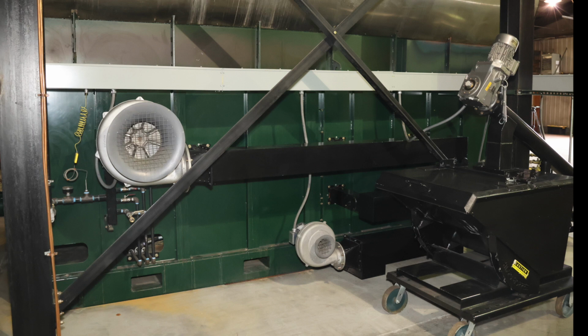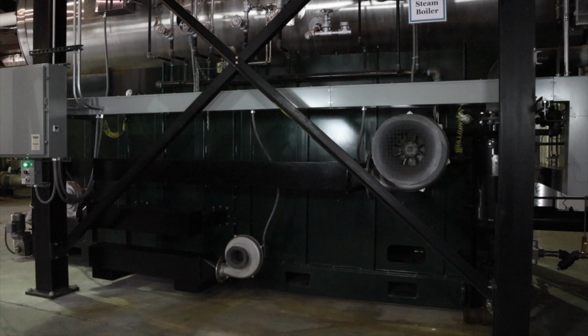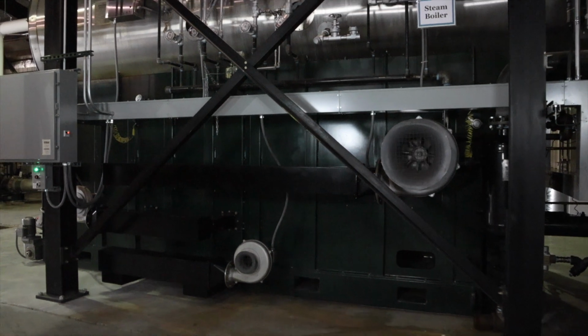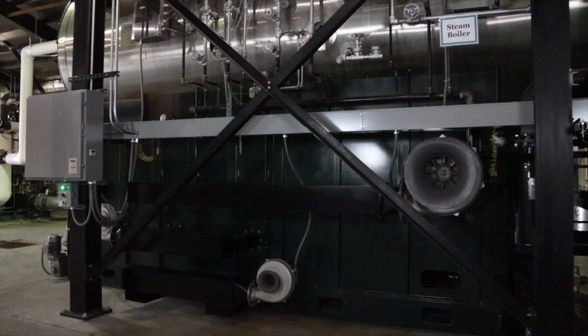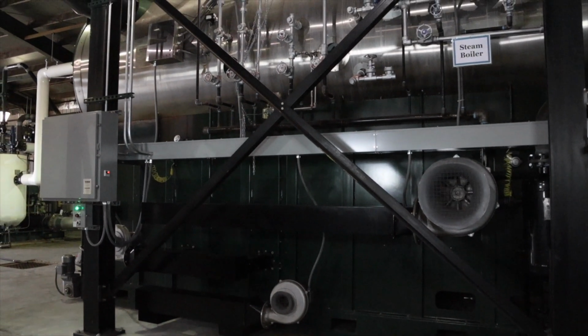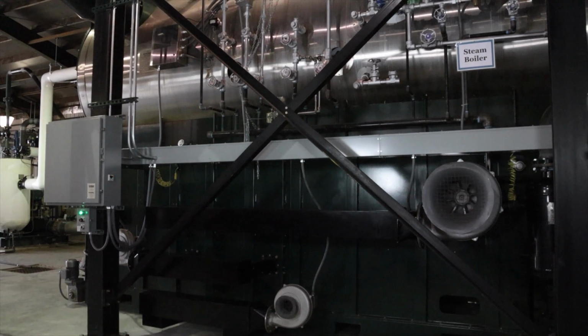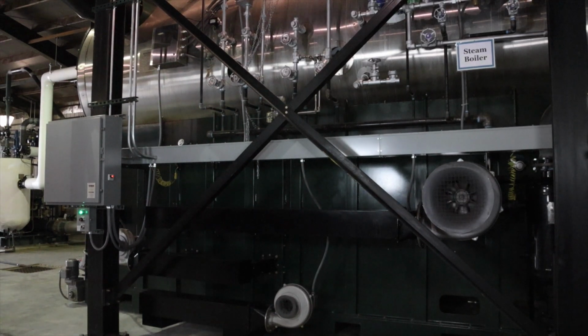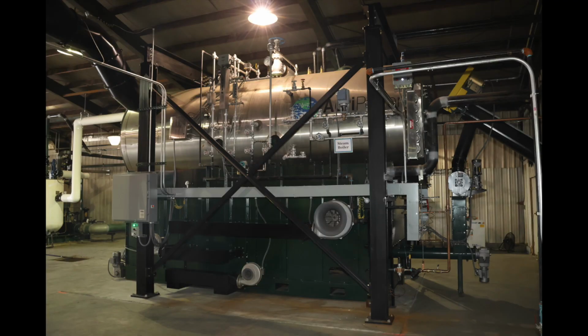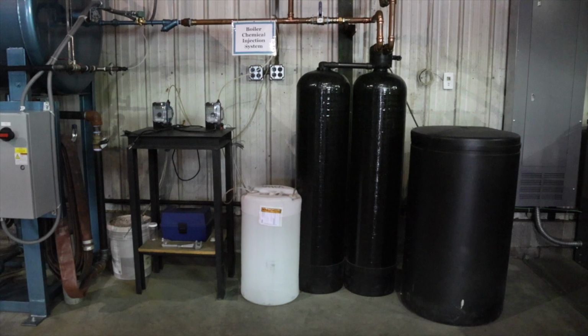The secondary combustion chamber, which is a chamber located directly above the primary combustion chamber or firebox, is used to hold the combustion gases for added residence time at high temperatures to lower and/or eliminate possible harmful stack emissions. Directly located above the secondary combustion chamber is our fire tube steam boiler. The boiler is equipped with all the necessary level sensors, valves, and monitoring equipment. It utilizes an air-operated soot blower system to reduce maintenance and improve efficiency.